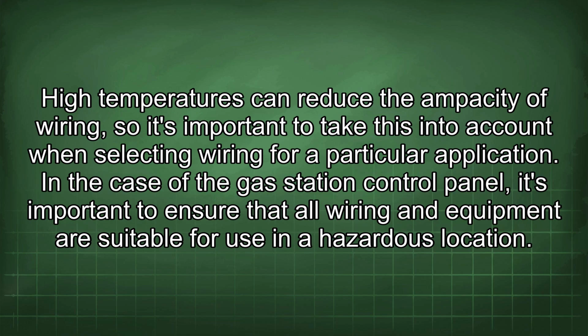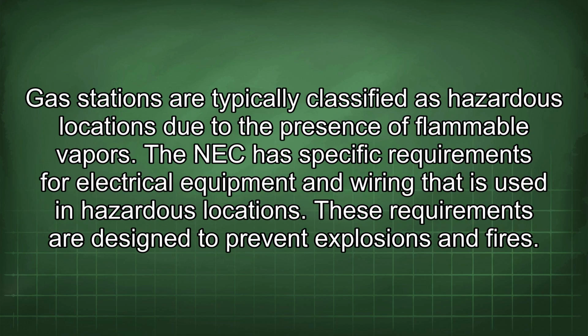a particular application. In the case of the gas station control panel, it's important to ensure that all wiring and equipment are suitable for use in a hazardous location. Gas stations are typically classified as hazardous locations due to the presence of flammable vapors. The NEC has specific requirements for electrical equipment and wiring that is used in hazardous locations. These requirements are designed to prevent explosions and fires.